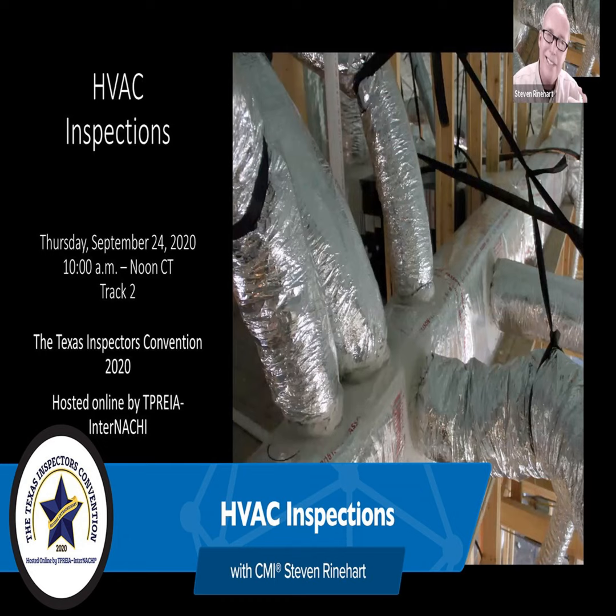Absence of combustion air in a closet. They're kind of saying it's not always a deficiency, because if you had a condensing furnace in the closet, you wouldn't need combustion air. So it does depend on the design, but unless it's condensing, it needs combustion air.